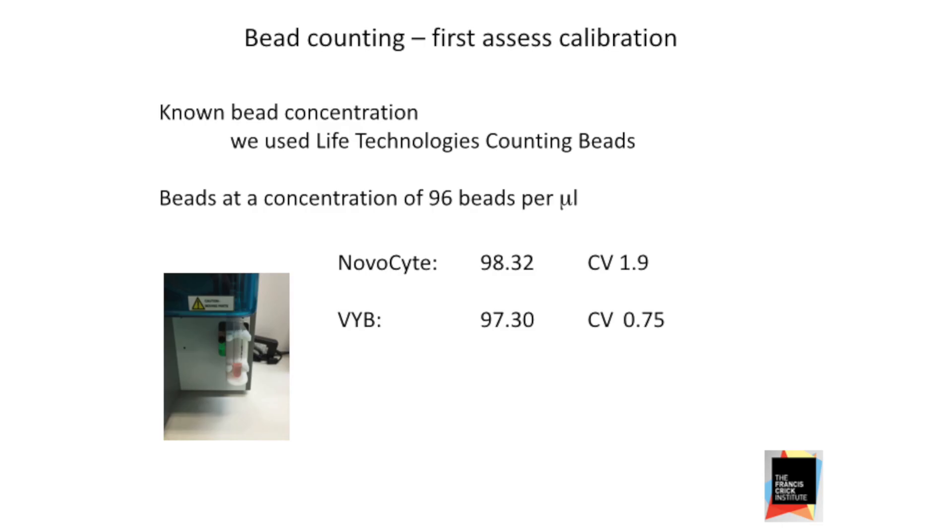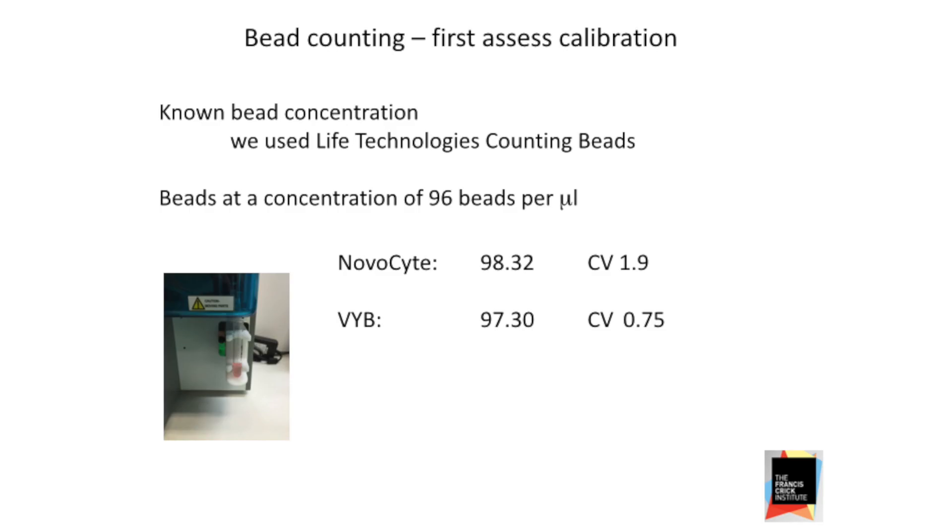So the first thing we did with the machine, we got some counting beads — Life Technologies beads that come with a known concentration — and ran those through two different machines. Most cytometers in my lab are not volumetric, but I do have a rival one, a MACSQuant VYB, so we have the perfect machine to compare with. Counting beads are actually notorious to handle, so we made sure nobody else touched that bottle. Handling them consistently — vortexing each time — is quite important, otherwise your count differs every time.